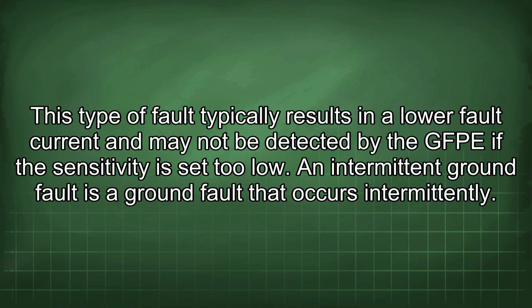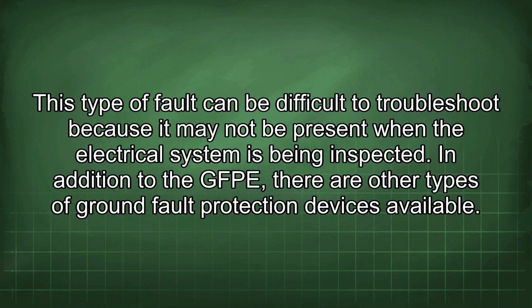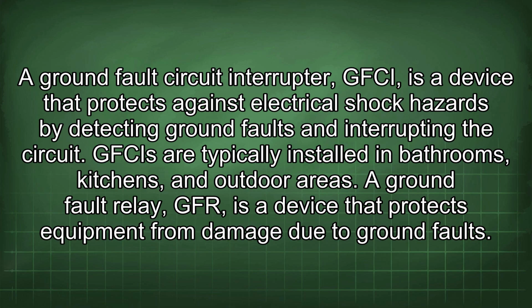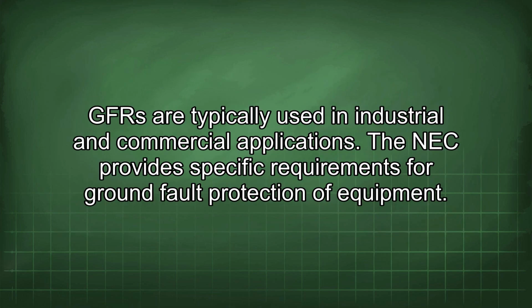An intermittent ground fault is a ground fault that occurs intermittently. This type of fault can be difficult to troubleshoot because it may not be present when the electrical system is being inspected. In addition to the GFPE, there are other types of ground fault protection devices available. A ground fault circuit interrupter, GFCI, is a device that protects against electrical shock hazards by detecting ground faults and interrupting the circuit. GFCIs are typically installed in bathrooms, kitchens, and outdoor areas. A ground fault relay, GFR, is a device that protects equipment from damage due to ground faults. GFRs are typically used in industrial and commercial applications.